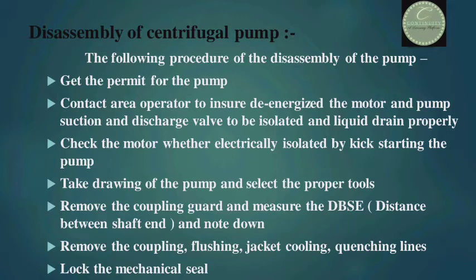Disassembly of the centrifugal pump procedure: Get the permit for the pump. Contact the area operator to ensure the motor and pump suction and discharge valves are isolated and liquid is drained properly. Check whether the motor is electrically isolated by kick-starting the pump. Take drawings of the pump and select proper tools. Remove the coupling guard and measure the DBSE — distance between shaft ends — and note it down. Remove the coupling, flushing jacket, cooling, and quenching lines, and lock the mechanical seal.